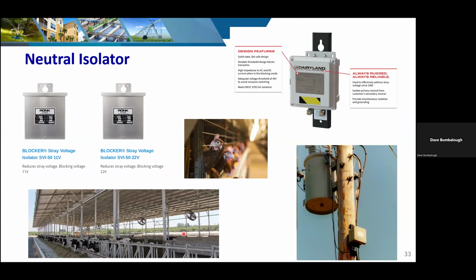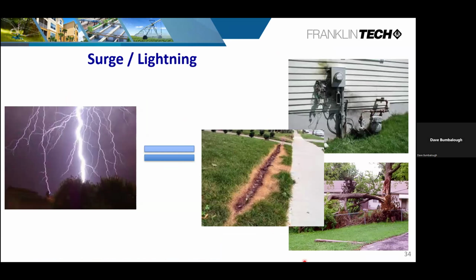And I'll guarantee it, if it's some kind of animal confinement like dairy farms and or poultry farms, they're going to see a big difference. Okay, a huge difference. Now the ones that I plucked off of here, there's two different models. One's rated for getting rid of about 11 volts off of the safety ground, and another one, it's a little bigger unit, will get rid of about 22 volts. If it's any higher than that, typically there's something else going on in the system, and you definitely want to make sure the power company's involved there, getting out there and resolving any issues they may have.